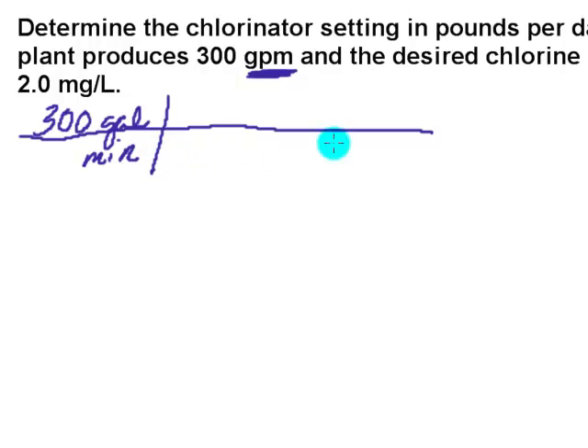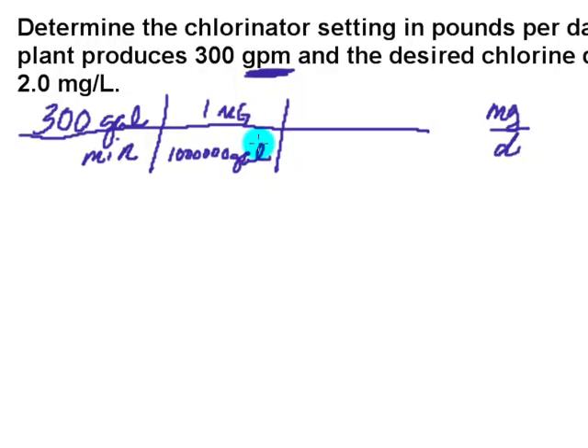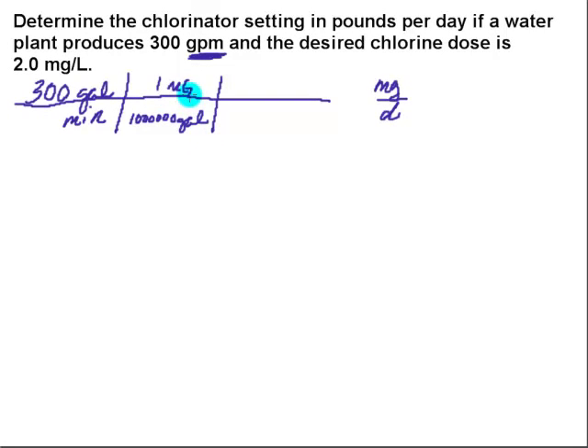I'm just going to wall that off, and where I want to end up with when I'm done is million gallons per day. So MGD is not all one thing, and neither is GPM, so million gallons per day goes underneath. Let's convert gallons to million gallons first. So I've got gallons up here for every 1 million gallons. And if what I'm doing here confuses you, go back and watch the unit conversion video, there's about a half hour that really explains this in detail.